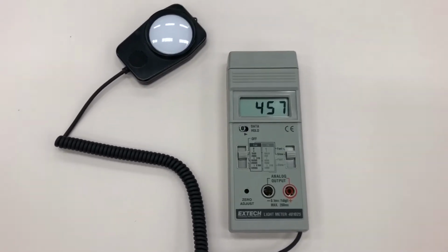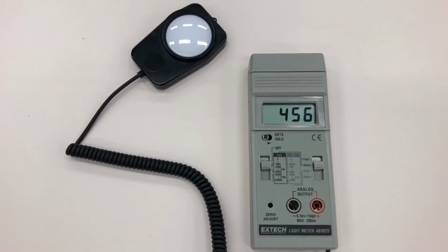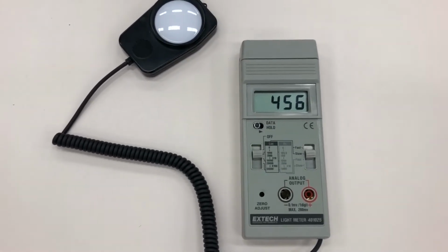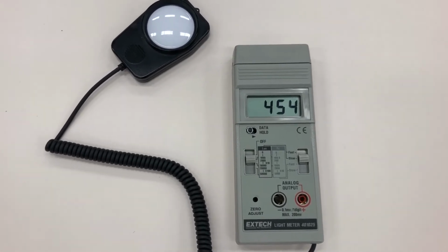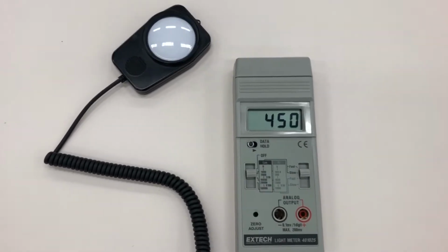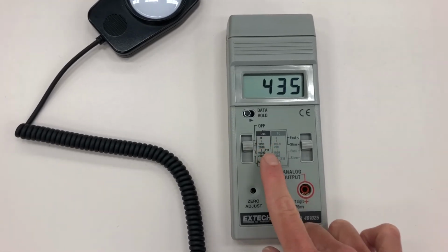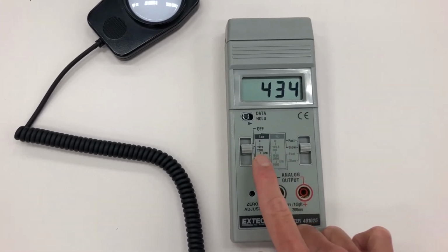And so here on this Extech light meter or lux meter that we have, you'll notice that the overhead light source right now is at approximately 455 lux. And just something else that I wanted to point out on the scale here is, we have lux here and we have foot candle here, and you'll notice the difference in the scale is approximately 10.